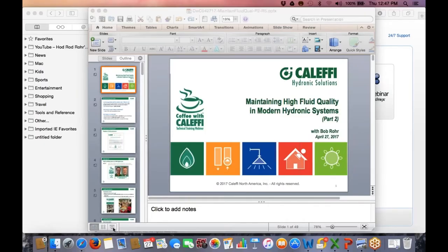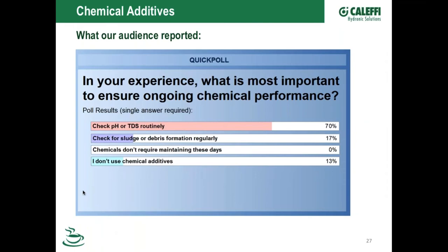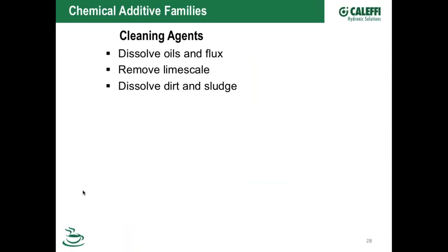Let me get back to where I was, because I want to talk more about glycol. One of the first, and I think most important steps, is when you put in a new system, you think about what's in that system. You've soldered copper pipe, so you've got flux in there, which most have chlorides or ammonia as a cleaning agent. You've got oil in there, you might have piped open air, there's assembly lubes, and when we put stuff together at Caleffi, we use Loctite, and there's probably Loctite inside some of the things we send out to you.